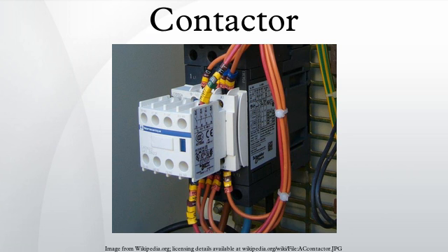NEMA standard contactor sizes are designated 00, 0, 1, 2, 3, 4, 5, 6, 7, 8, 9. The horsepower ratings are based on voltage and on typical induction motor characteristics and duty cycle as stated in NEMA standard ICS2. Exceptional duty cycles or specialized motor types may require a different NEMA starter size than the nominal rating. Manufacturer's literature is used to guide selection for non-motor loads, for example, incandescent lighting or power factor correction capacitors.